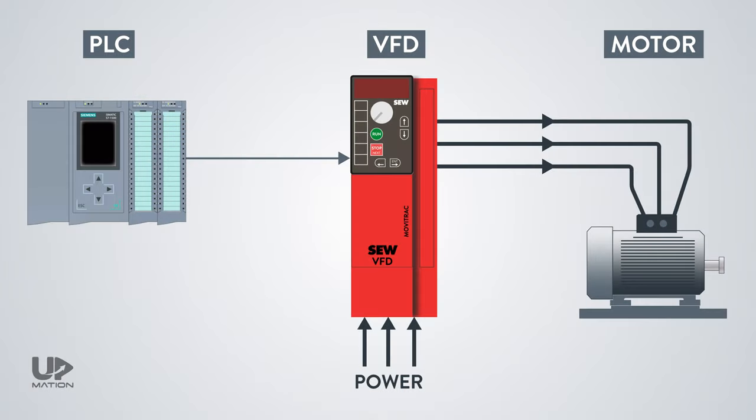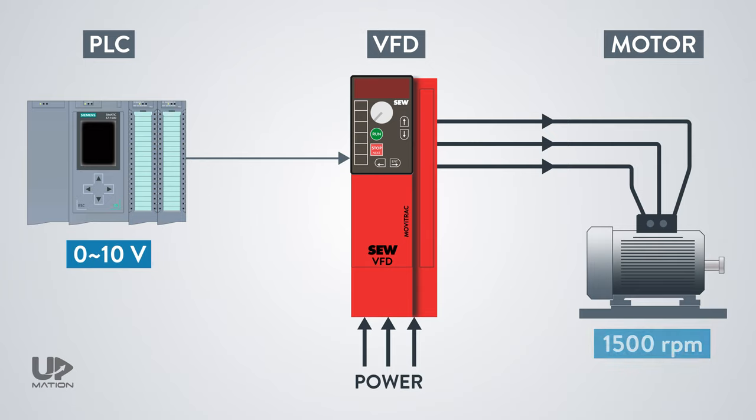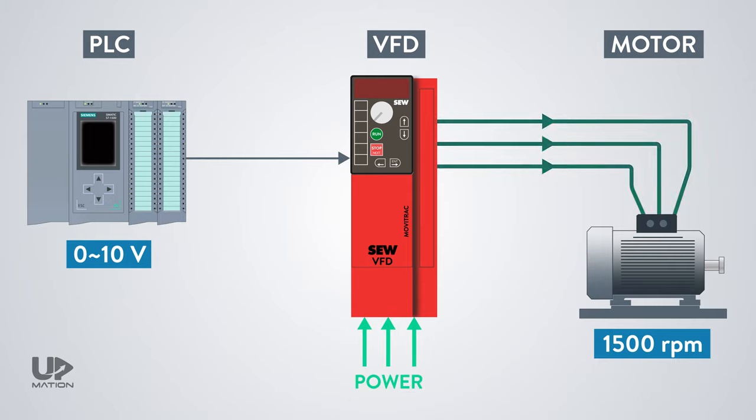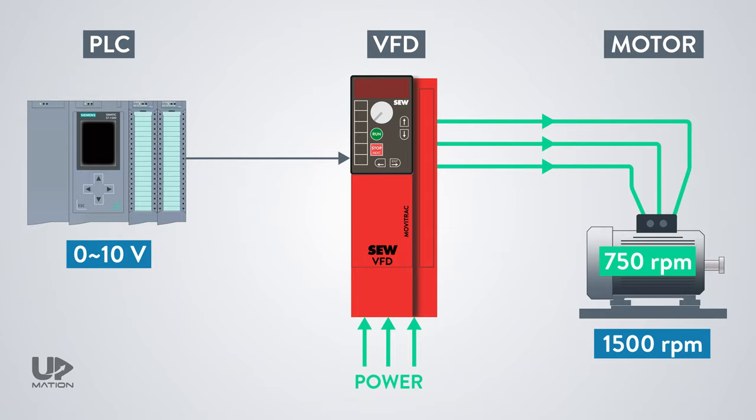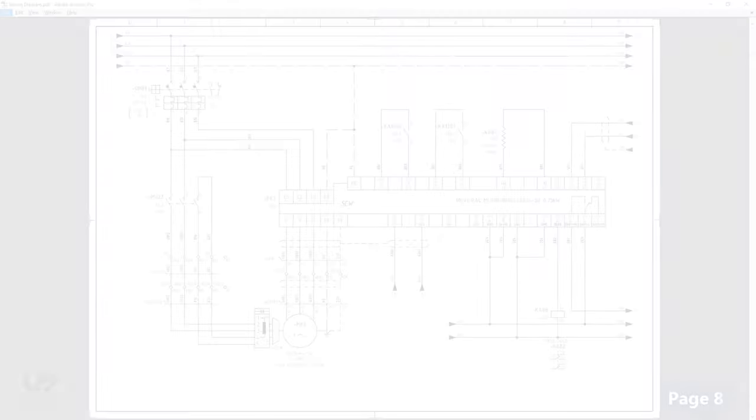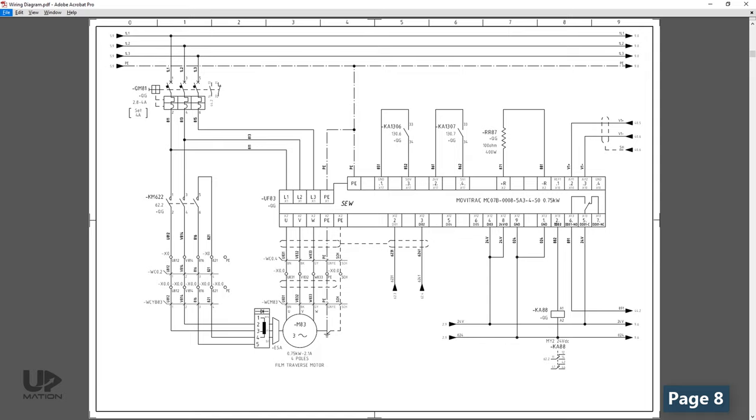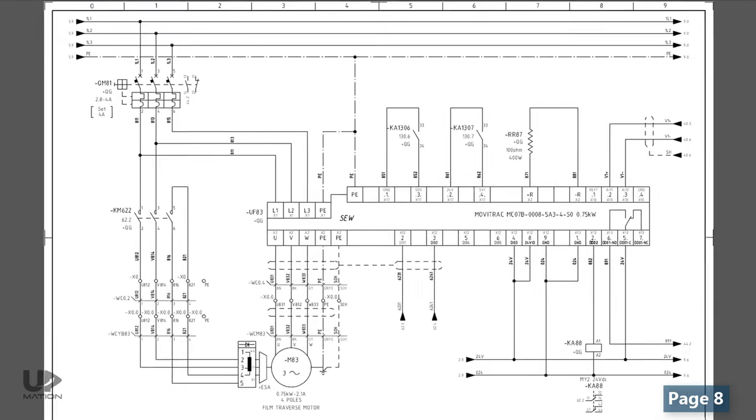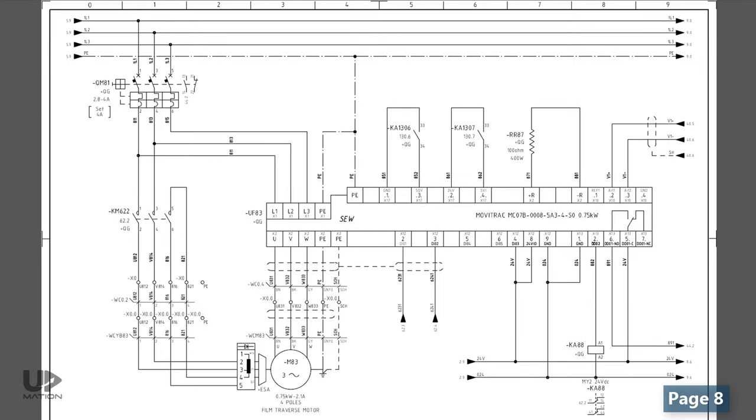For instance, consider that the speed reference voltage is between 0 to 10 volts and the motor nominal speed is 1500 RPM. When the PLC card sends out a 5 volt signal to the VFD, the VFD will adjust the power to the motor so that it will rotate with 50% of its nominal speed which is 750 RPM. The rest of this page is related to some interlocks or conditions.